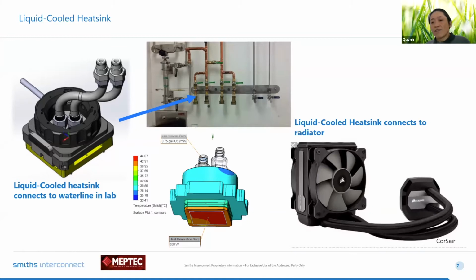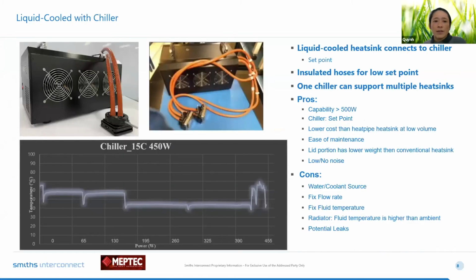Now, for those lab facilities that do not have a water line available, this lid can be connected to a radiator for the liquid cooling option. Another option is that the lid can also be installed with a chiller. With the chiller, we have the option to control the set point so that it can improve the dissipating capability. It can set the temperature below ambient.